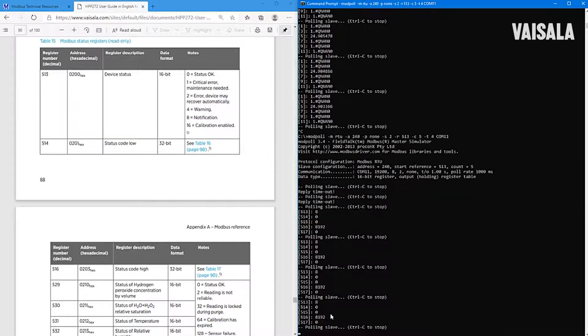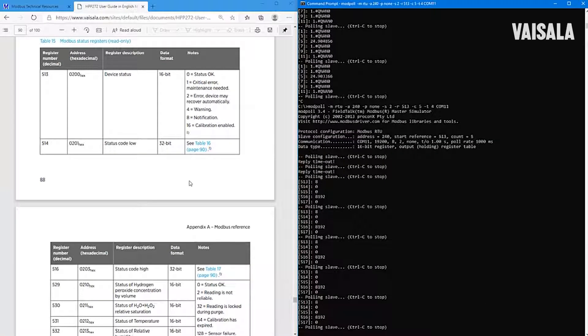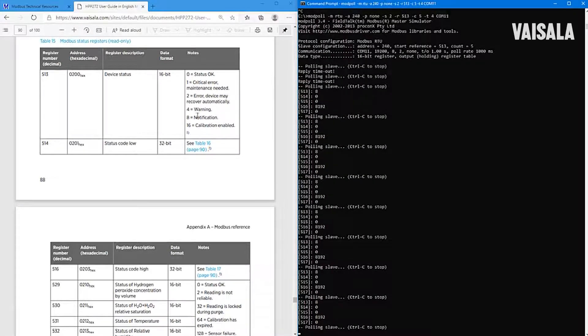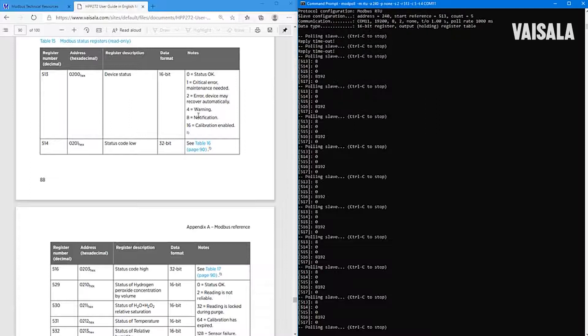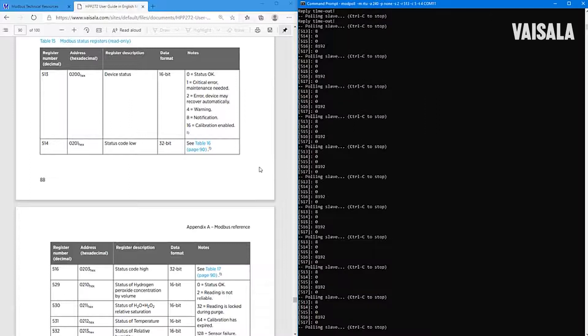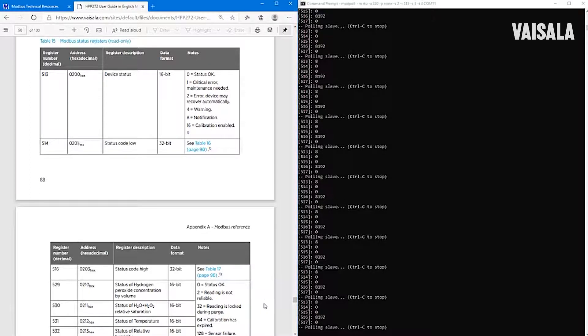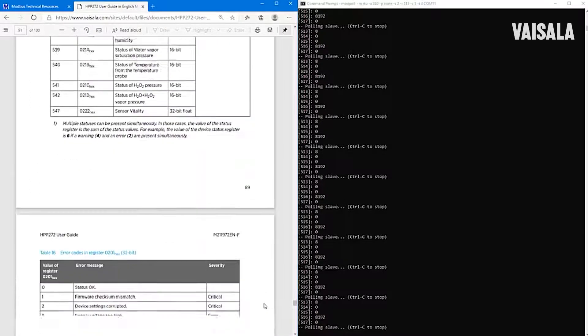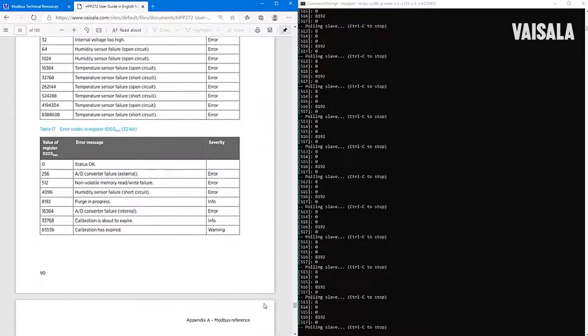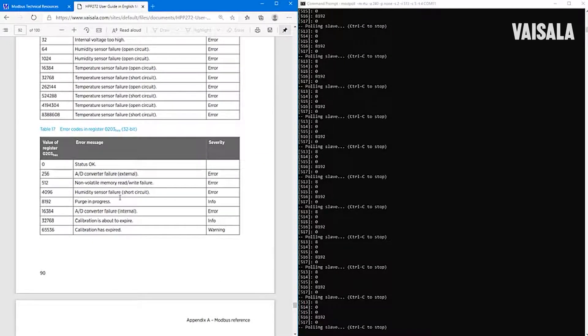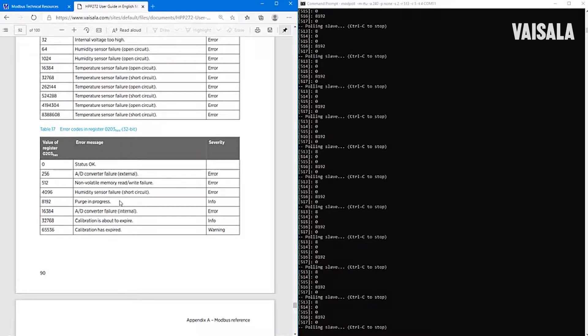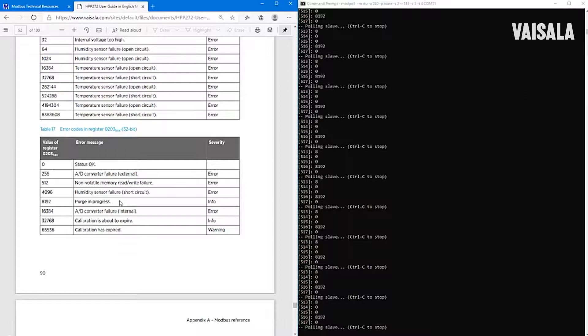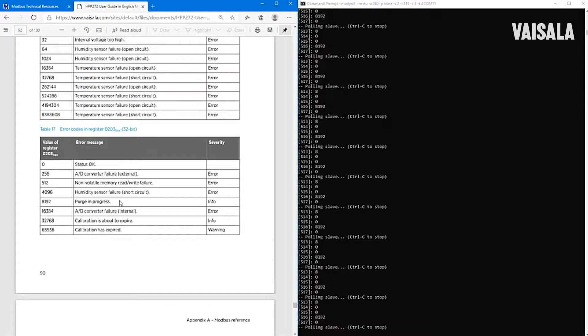And now we can see that 513 is showing that there is some kind of notification. And this 516 register tells us something. And we can check the error codes here, and here it says that the purge is in progress. So let's wait until this purge is completed, and then we can read the other values also.